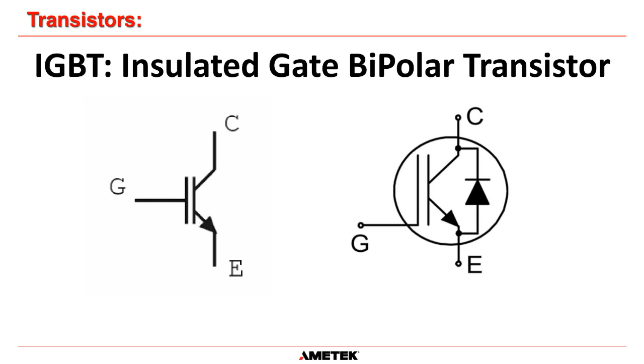The diode allows us to get rid of that inductive kickback. We have a capacitor back here, and it allows the system to self-discharge that kick into our capacitor bank rather than destroy the IGBT, which can happen. So that's why the diode is inserted by the manufacturer, to prevent inductive kickbacks from damaging the IGBT.